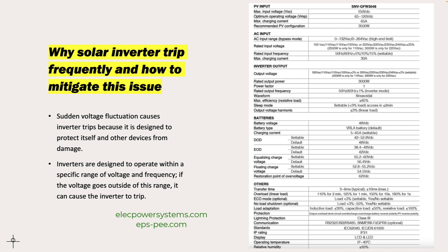Sudden fluctuations in grid voltage can cause issues for inverters and other electrical devices. When the grid voltage goes up or down suddenly, it can cause the inverter to trip because it is designed to protect itself and other devices from damage. Inverters are designed to operate within a specific range of voltage and frequency, and if the voltage goes outside of this range, it can cause the inverter to trip by shutting off when the voltage is too high or too low.